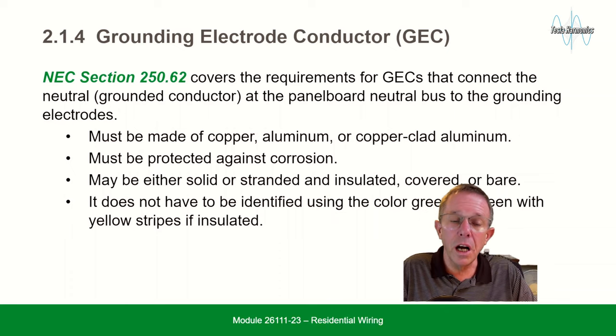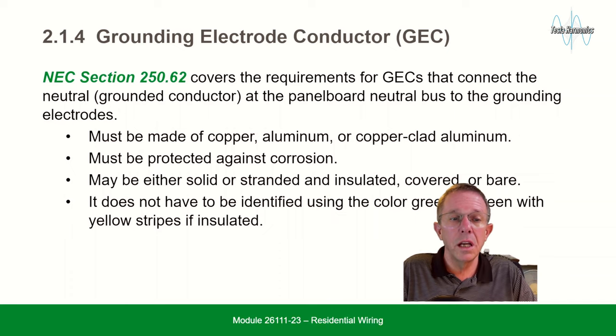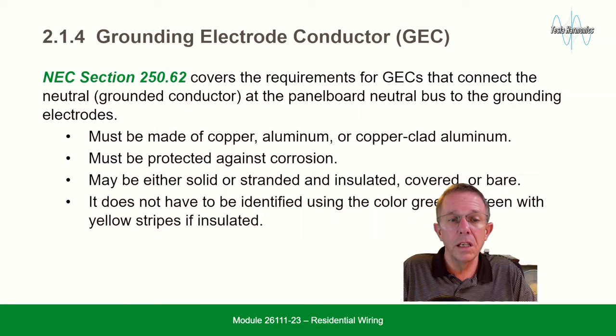The GEC must be made of copper, aluminum, or copper-clad aluminum. It must be protected against corrosion, and it may be either solid or stranded, and insulated, covered, or bare. It does not have to be identified using the color green or green with a yellow stripe if insulated.